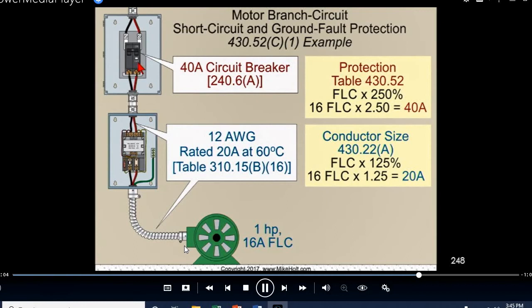So there are people, let's wrap it here, there are people that have a major problem. Let's look at the illustration here. You size the wire to 125%. You size the breaker to 250%, which means your protection is always going to be 2 times the size of the wire. That's how the numbers work, no matter how many times you try it. And this protects the motor and the conductors against short circuits and ground faults. That protects the overloads, and we're fine.